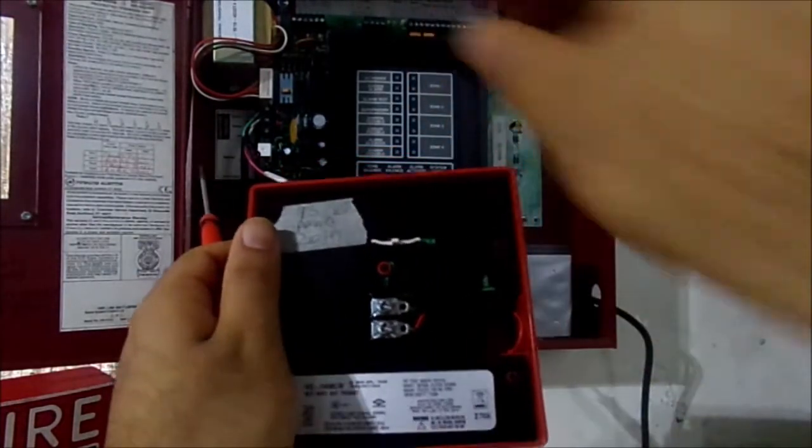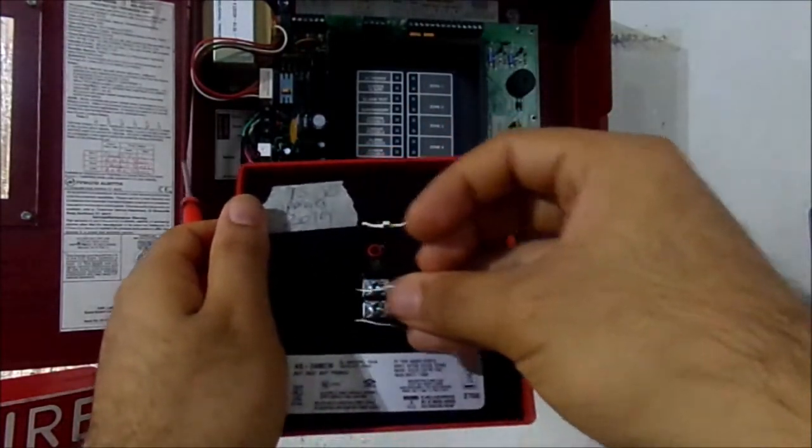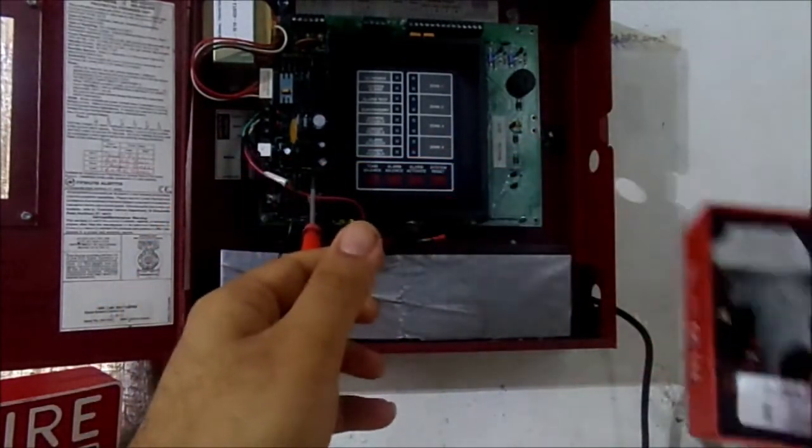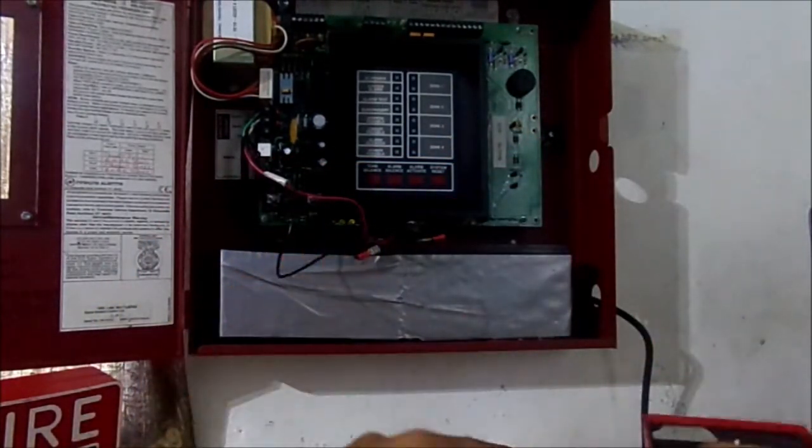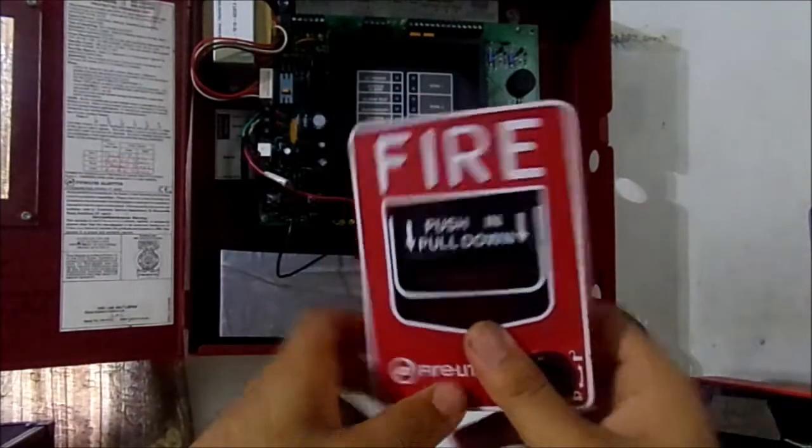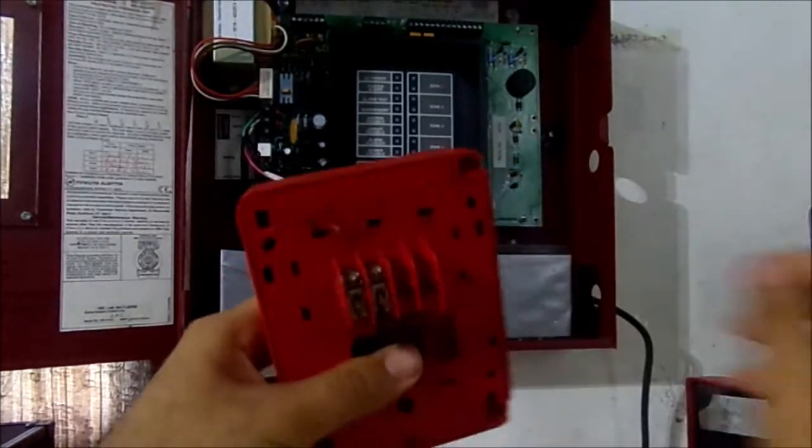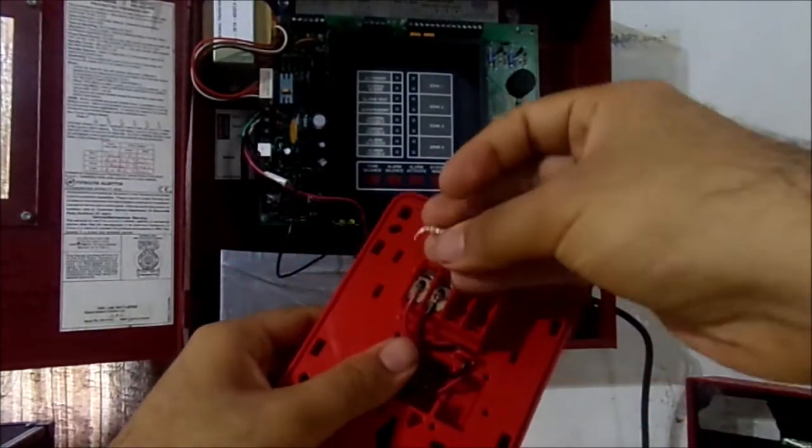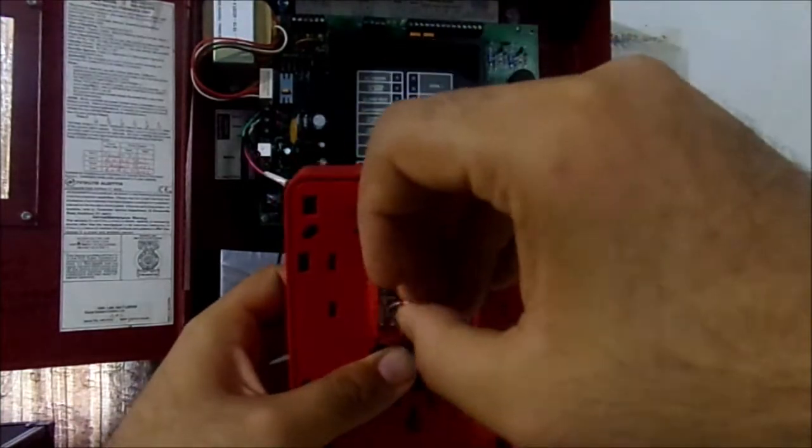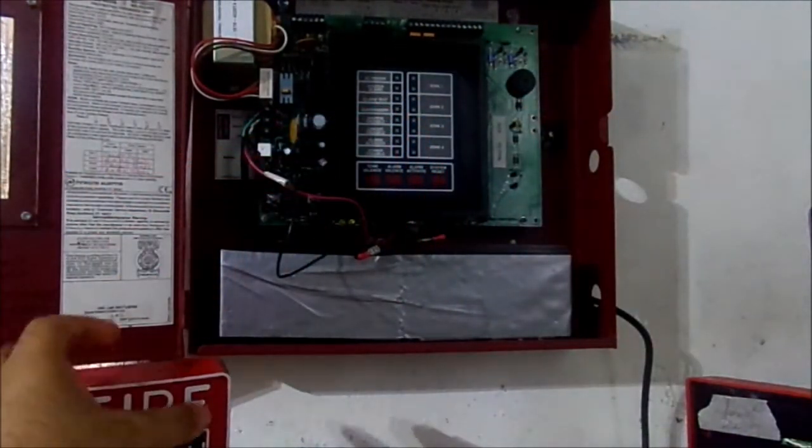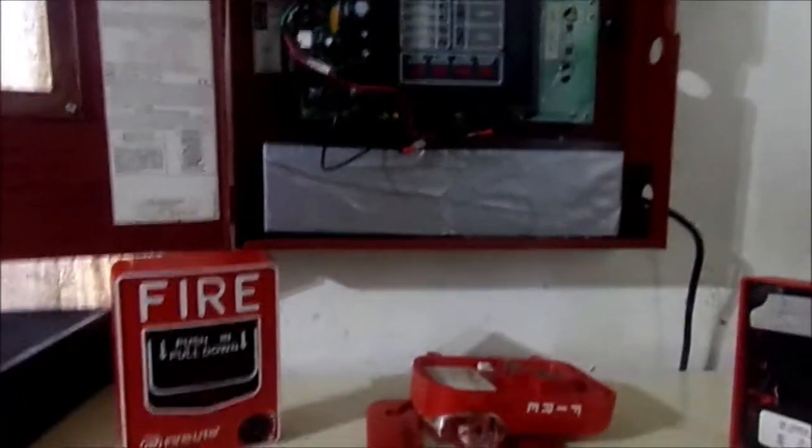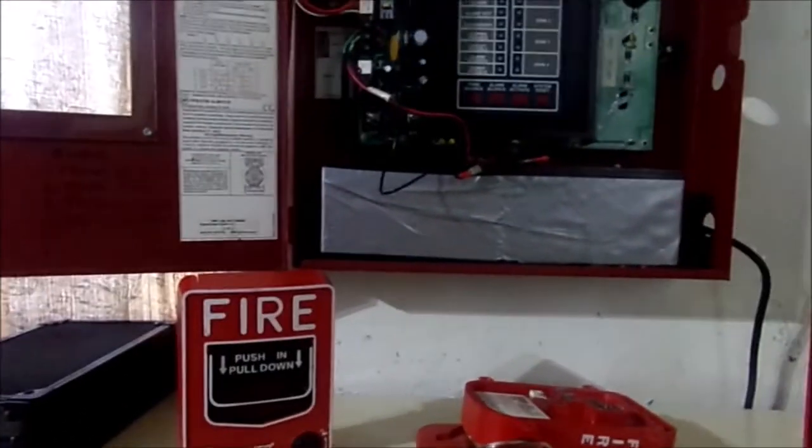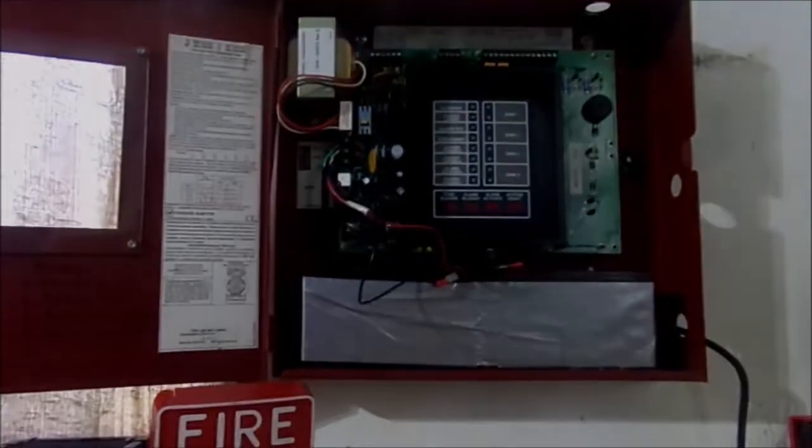This is useful so that the fire panel can see, oh, there's a resistor in this line and it doesn't go in trouble. Simple to wire. Same thing as the pull station over here. So, there's two terminals over here. And at each end of the device, you put the resistor here and you tighten the screw. And it's the same thing pretty much. Now I'm going to finish wiring this up really quick. And I'm going to get back to the video.